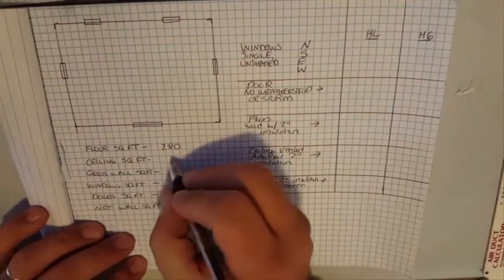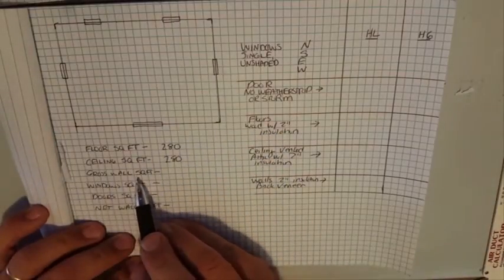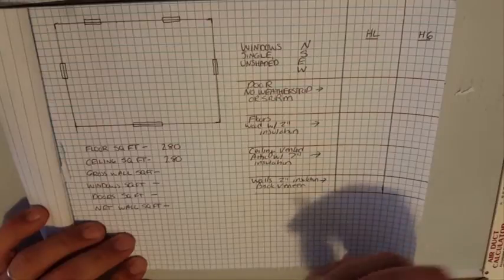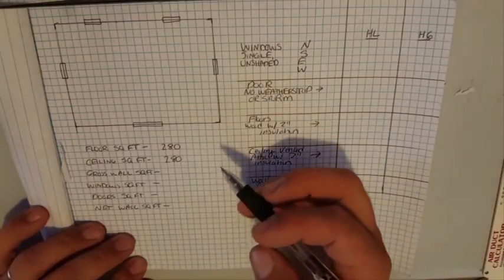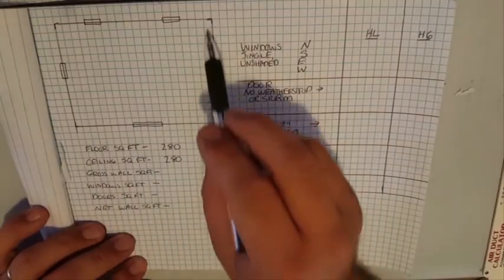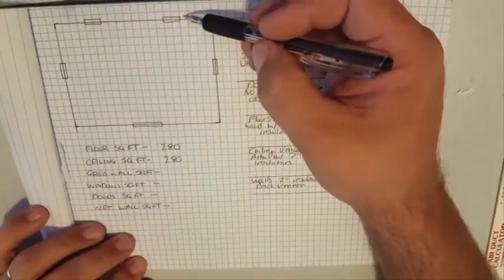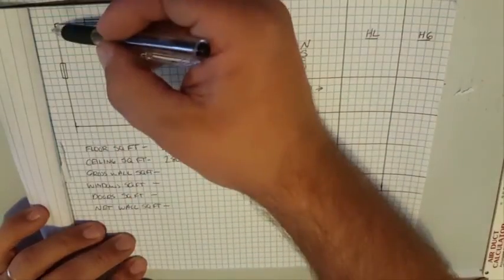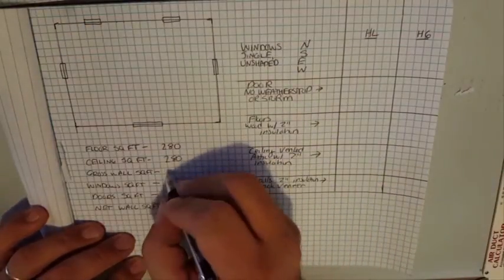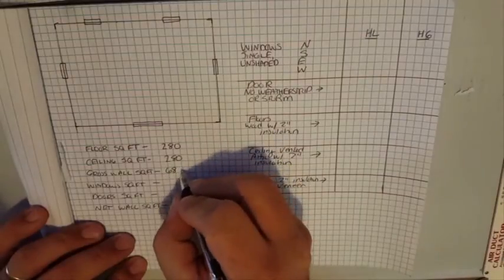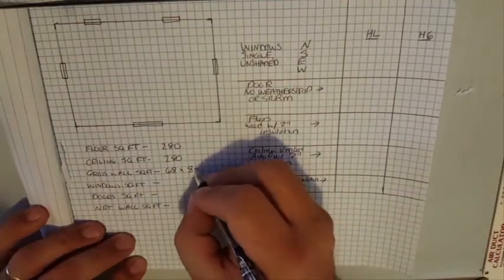Our gross wall square foot - what that is is just the area of the wall. We didn't mention it, but we'll say our wall height is eight foot, so our ceiling height in our rooms is eight foot. What we're going to do is we're going to figure out how many linear feet go around this building, and that's 20 plus 20 is 40, plus 14 is 54, plus 14 is 68. So we have 68 linear feet. We're going to just multiply that out - 68 linear feet times eight foot ceilings - basically the area of our walls.